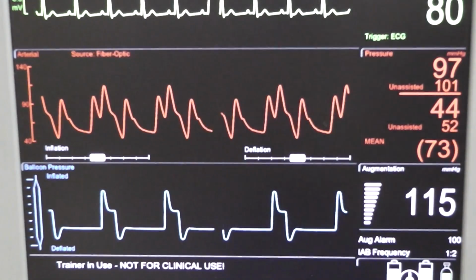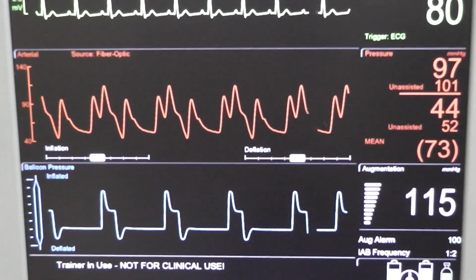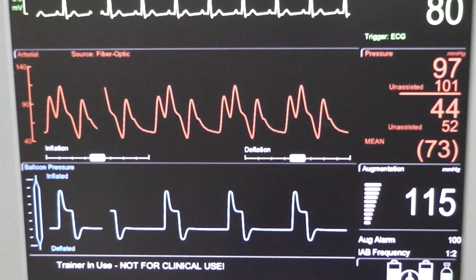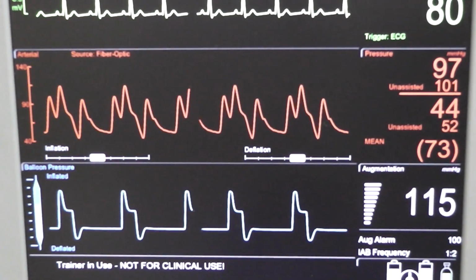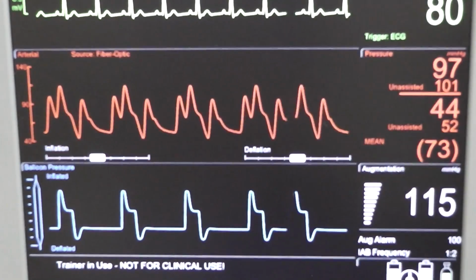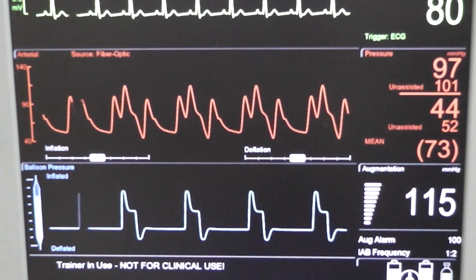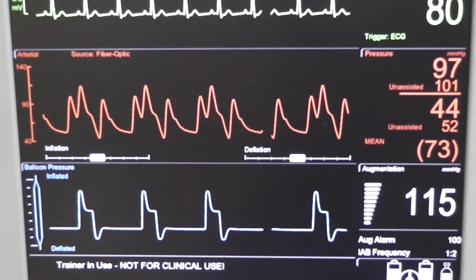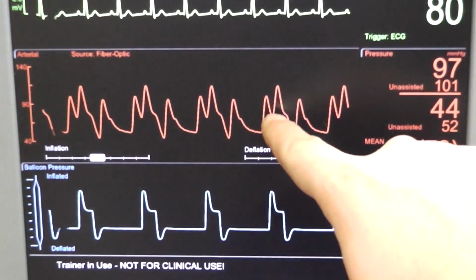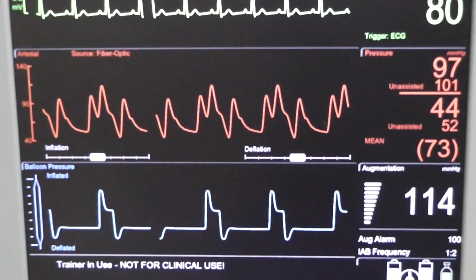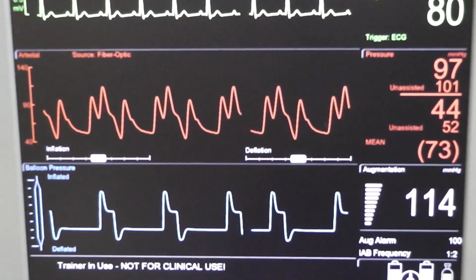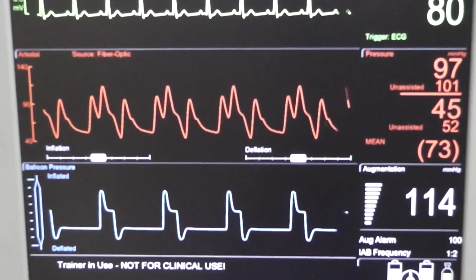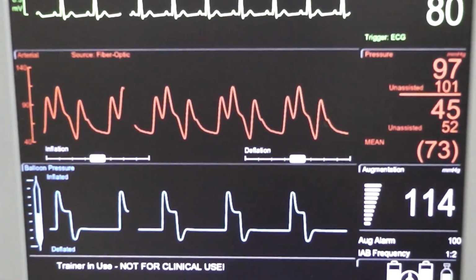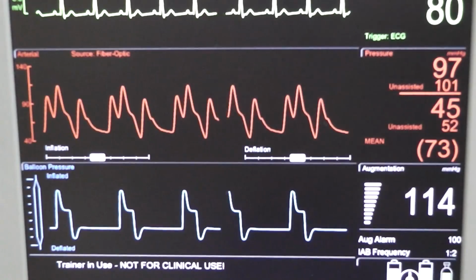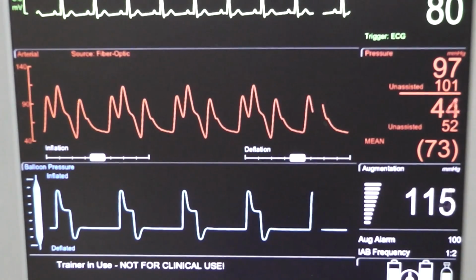Okay, now we're looking at the upper screen, and I have the console set to semi-auto mode, so we have some control, some manual control, and I also have it set to 1 to 2 frequency. So you can see here that every other trigger point, the balloon is inflating. So there's a balloon inflation. And I'm going to start adjusting some of these manual settings so that we get to that most efficient point that I've been referring to.